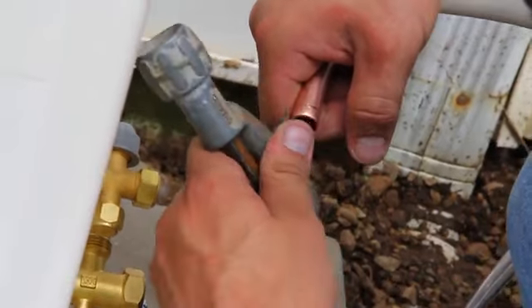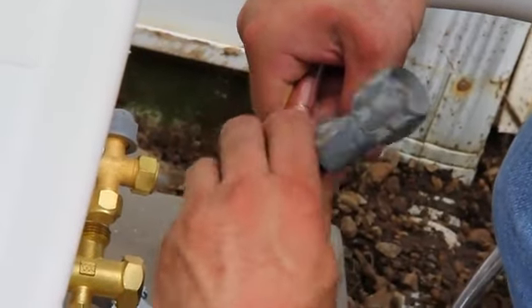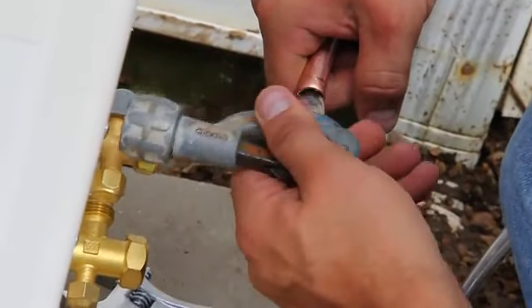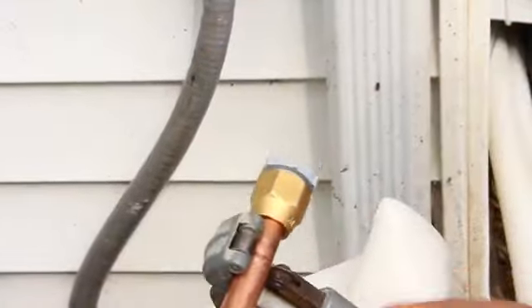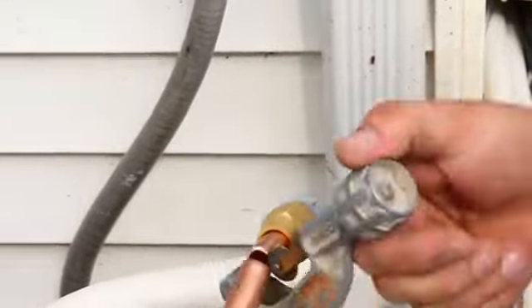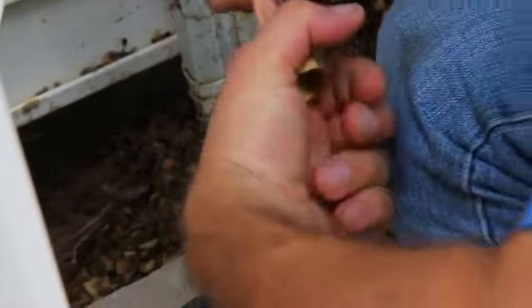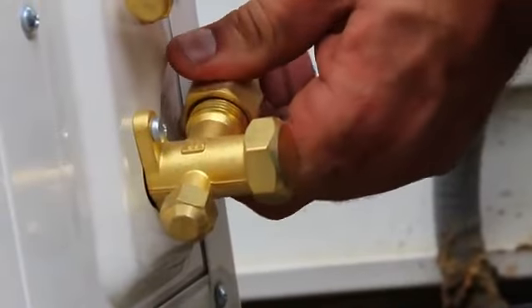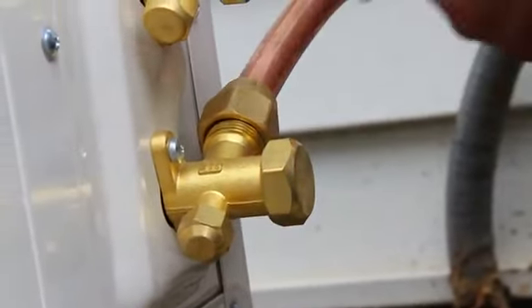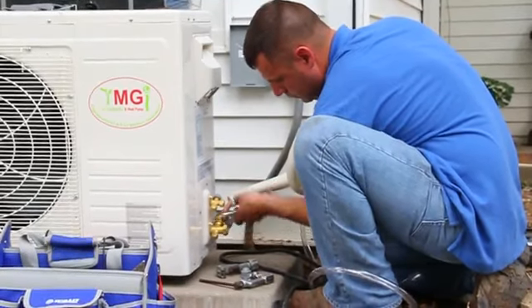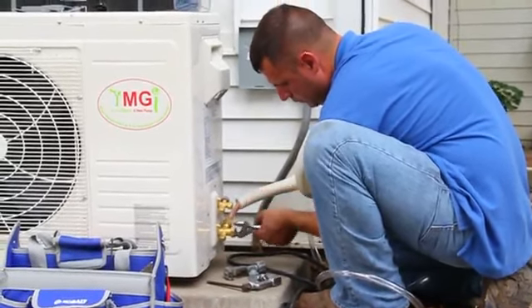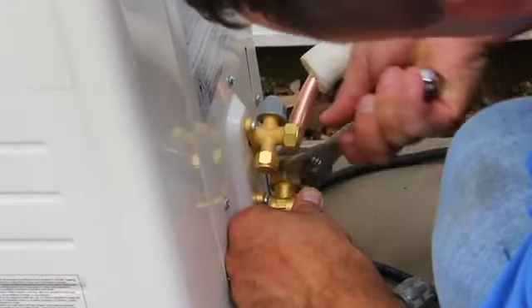After you cut the copper tubing, be sure to clean the interior of the tube so there are no fragments remaining inside from the cutting process. Excess material left over may cause corrosion. Also, cut carefully so you do not dent the copper tubing. Next, connect the refrigerant tubing to the condenser. Tighten the flare nuts to the torque specifications according to the installation manual. Do not over-tighten the nuts.